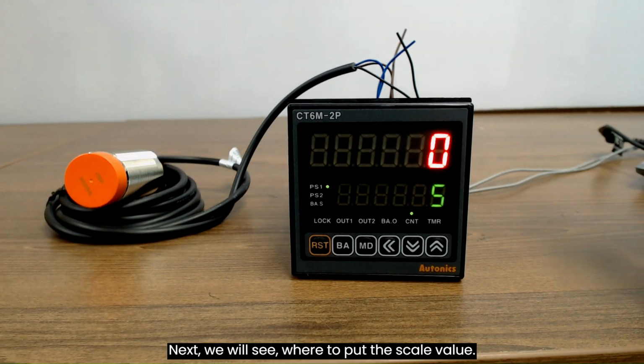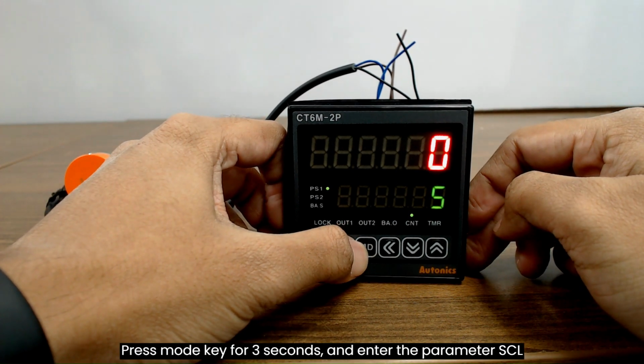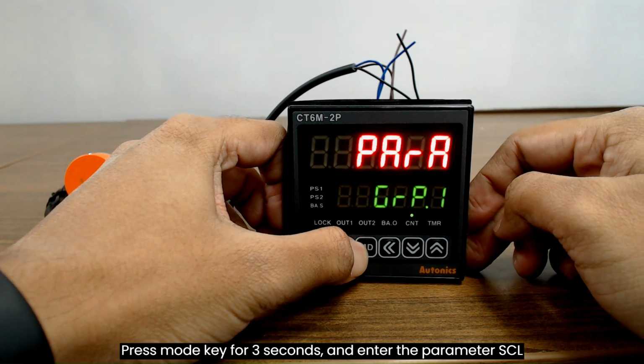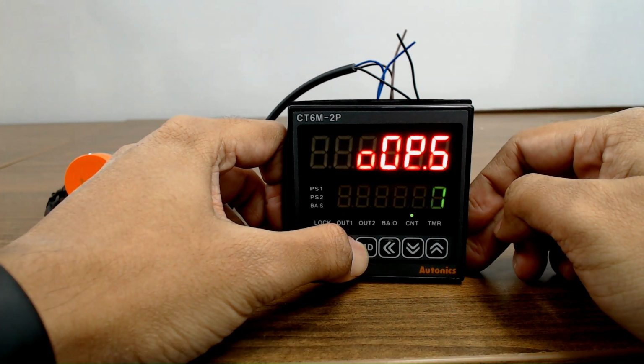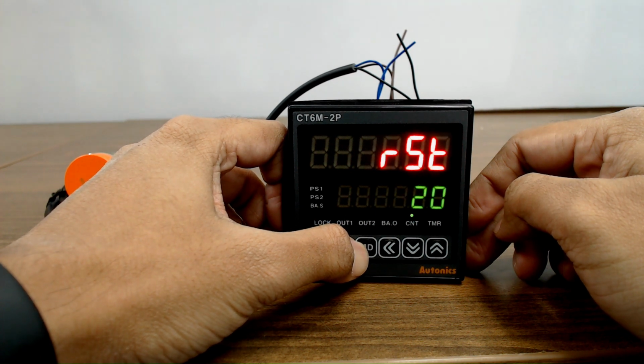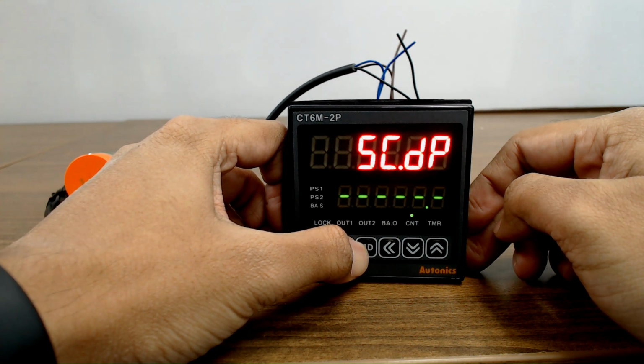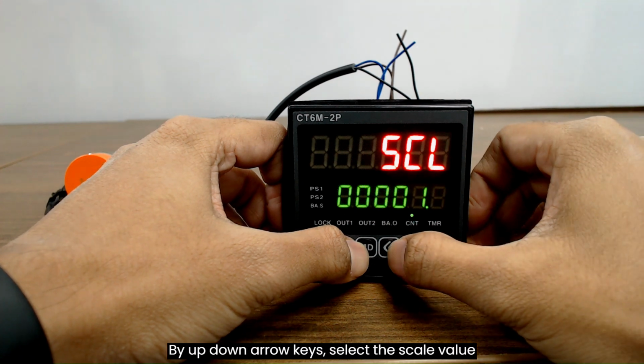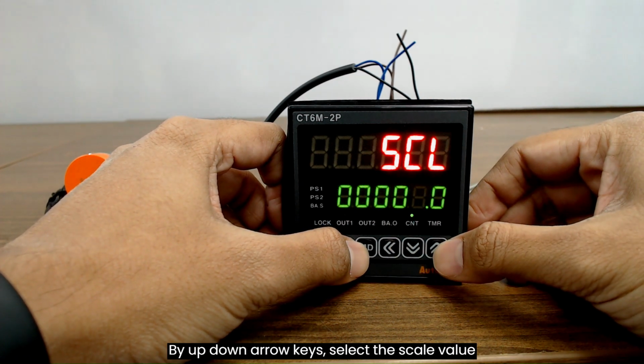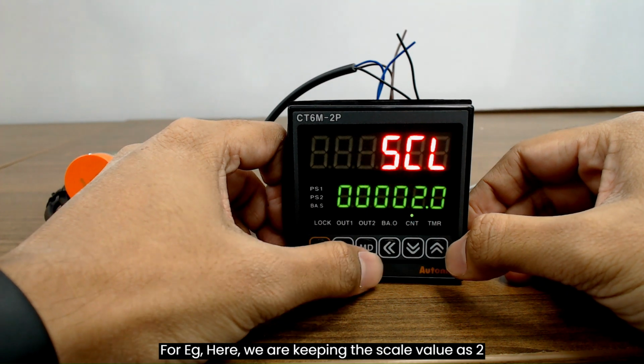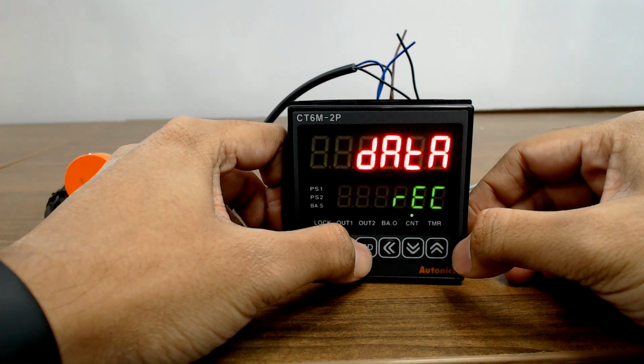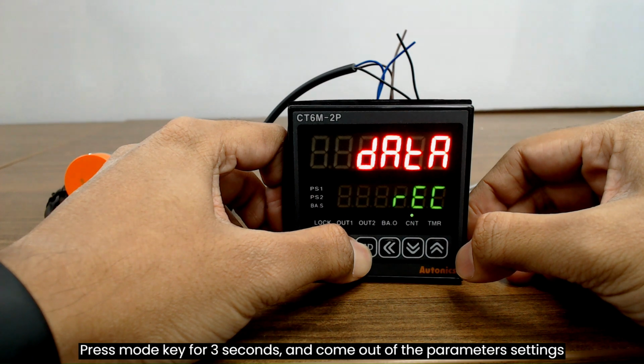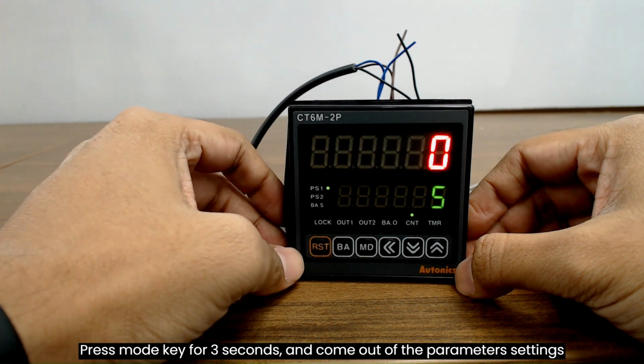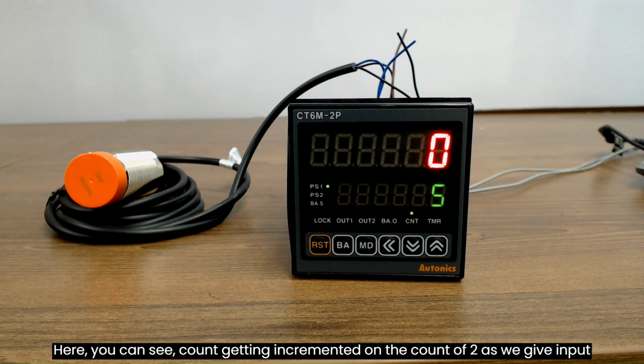Next, we will see where to put the scale value. Press mode key for 3 seconds and enter the parameter SCL. By up-down arrow keys, select the scale value. For example, here, we are keeping the scale value as 2. Press mode key for 3 seconds and come out of the parameters settings. Here, you can see count getting incremented by 2 as we give the input.